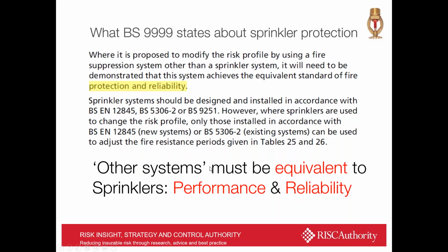And also, where they have been mentioned, this is a phrase out of BS 9999: where it is proposed to modify the risk profile by using a fire suppression system other than a sprinkler system, it will need to be demonstrated that this system achieves the equivalent standard of fire protection and reliability. Now, the fire protection bit is quite easy to generally demonstrate in the laboratory. You can tweak and play with any system to make it good. But reliability is a very different thing altogether, and that is generally earned over the years of refining, tweaking, really the development of pedigree, I suppose, of a system.